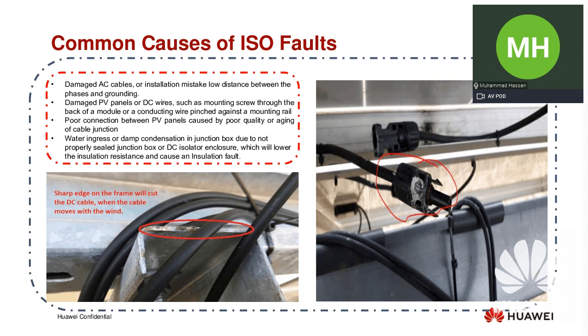Here are some ISO fault causes. As you can see, these ISO faults are very common in the UK market. These faults come from installation issues, where the installers are not focusing on the small things. They neglect the small things during the construction of the site, and later it starts damaging the product or creating problems for the customer. So whenever you go to a site, just oversee how things are installed. If you find any problem, inform the installer and try to fix it as soon as possible to avoid any damage, or loss of energy or production, with those inverters.